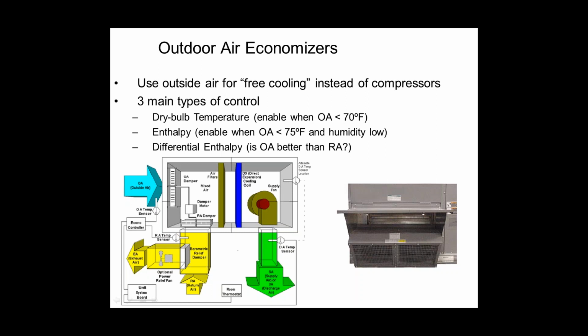Differential enthalpy, which would be the third type, is just like regular enthalpy, except I'm going to look at the temperature and humidity of the outside air, the temperature and humidity of the return air, and I'm going to decide who's cooler and drier, and whichever one is cooler and drier, I'm going to use that airflow stream, right? Because air going through my supply fan can only come from one of two places, the outside air louver or the return duct. So if I want cooling, and I only got two places to pick it from, whoever's cooler and drier, I'm going to take that airflow. And then I'll just use the compressors to supplement that as needed.